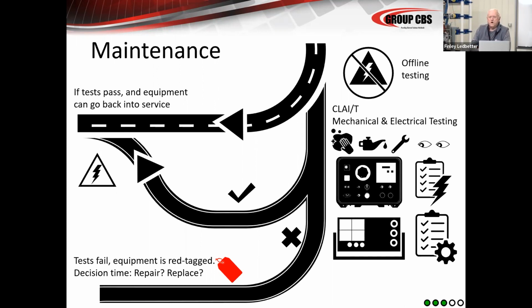That period where they start to wear out is usually conceived around the wear limits of the circuit breaker. The contacts are changing. The contacts are wearing. At a certain point, the wipe springs, which this paper does a very good job discussing, are there to hold pressure on the interrupters to stop popping forces from damaging the breaker if you see an overload. At a certain point, those wipe springs can no longer maintain the proper pressure on the interrupter, and they will possibly damage themselves if they're called upon to operate in an overload situation. Or possibly they will not interrupt a full, they always say bolted fault. You never see a bolted fault. Very seldom do you see a full bolted fault.